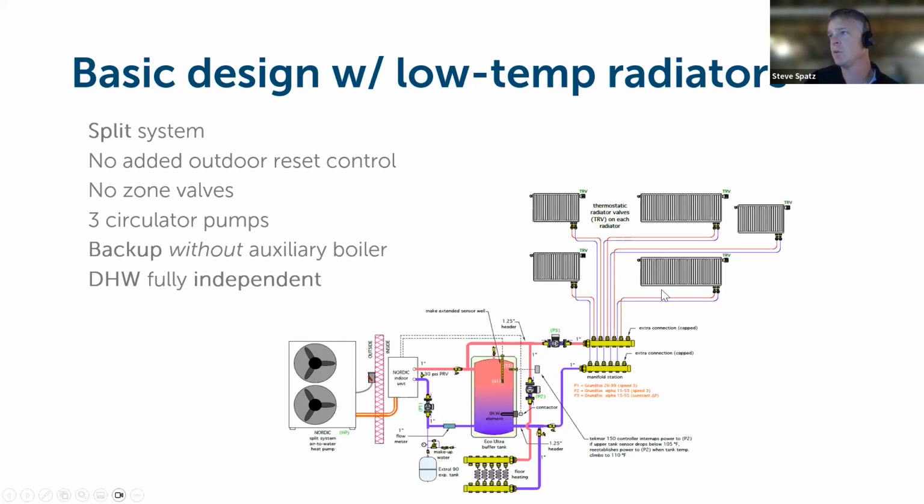And in this example, you've got multiple different panel radiators that are fed throughout the house, home run back to a manifold. So this is not a looped pipe system throughout the house. This is individual home runs back to a manifold where you get very specific control over the delivered BTUs and the flows necessary, because there's different flow capacity for this panel radiator right here than there is for this one. That's controlled in this type of a system.